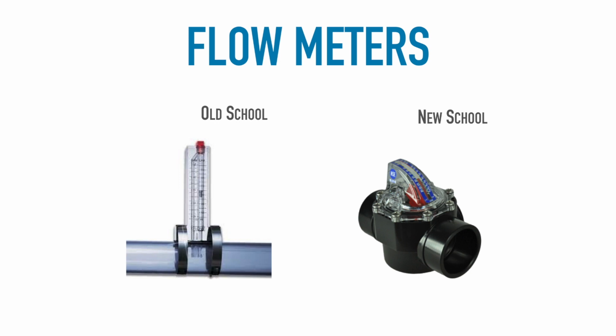These work, but believe it or not, according to spec, these are required to be installed on 6 feet of straight pipe in order to be accurate, or as accurate as possible. Now, let's be real. How many of us have 6 feet of straight pipe inside of our systems? The majority of us are lucky to have 1 foot of straight pipe to install on these, let alone 6. So as a result, we're getting very inaccurate numbers off of these old school flow meters.